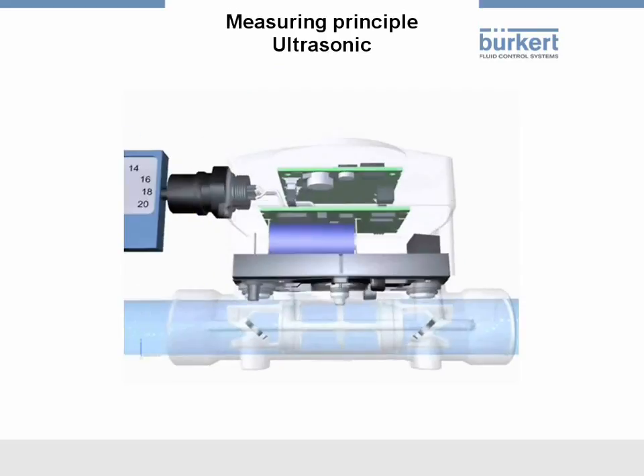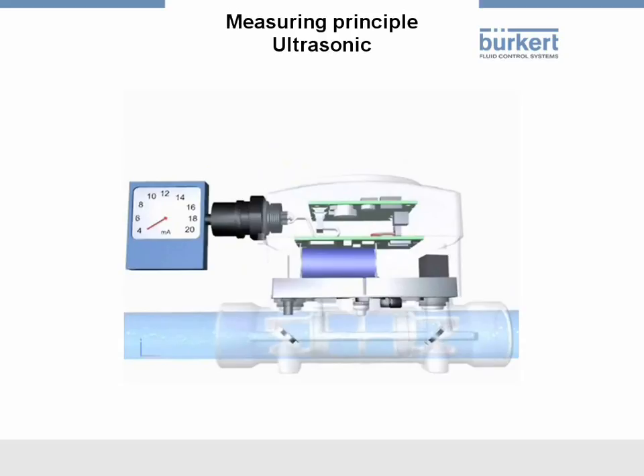In flow measurement by means of ultrasonic, there are two ultrasonic transmitter receivers at a specific distance L in the measuring pipe. They both send an ultrasonic signal to the other receiving point. These signals are reflected by two deflecting mirrors located in the center of the pipe opposite the transmitter receiver and are thus directed to the other receiver. The electronic circuit determines the propagation time of the two signals between the ultrasound transmitter and receiver.